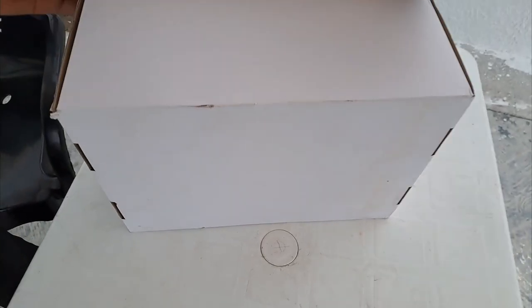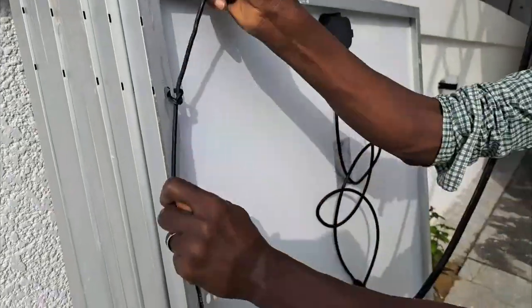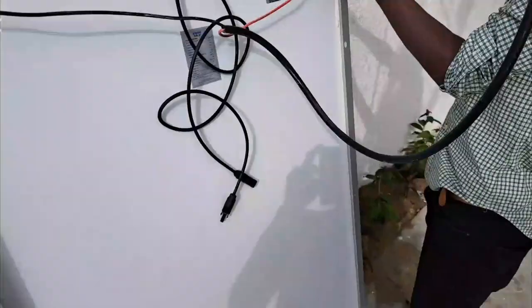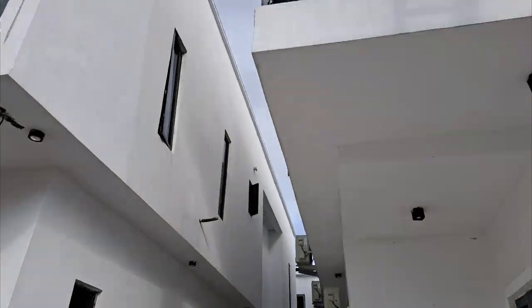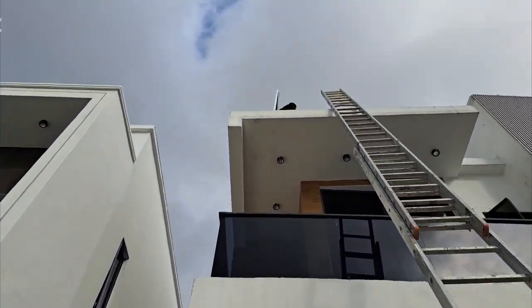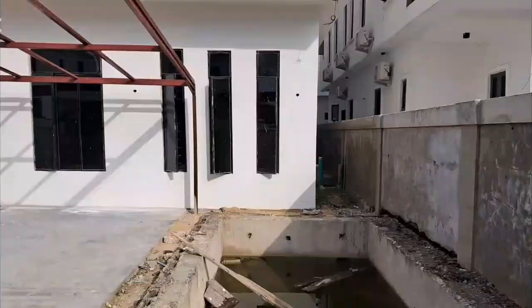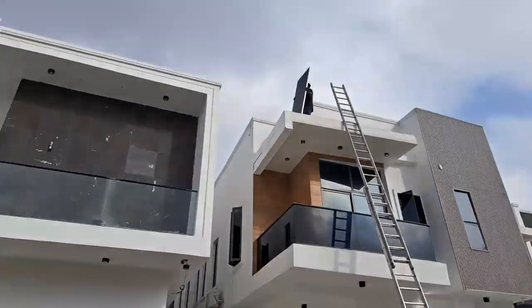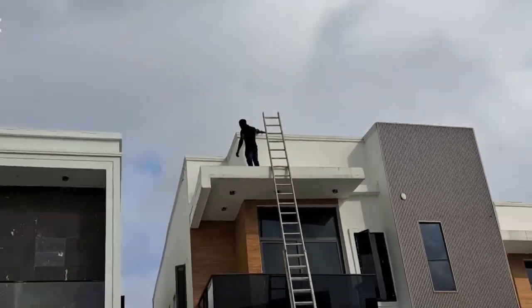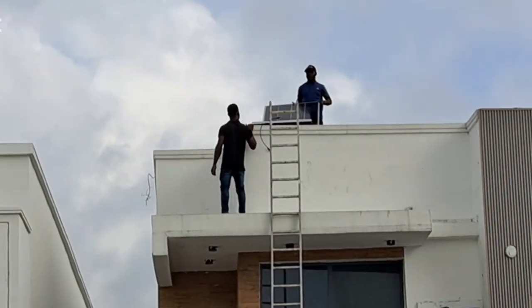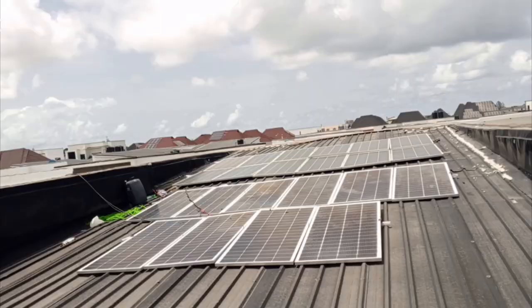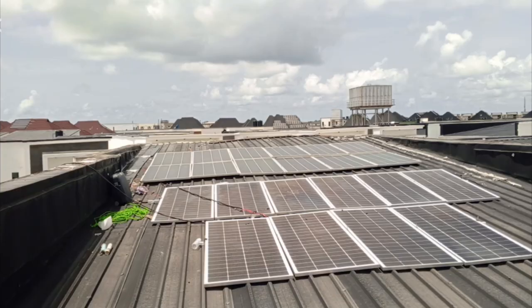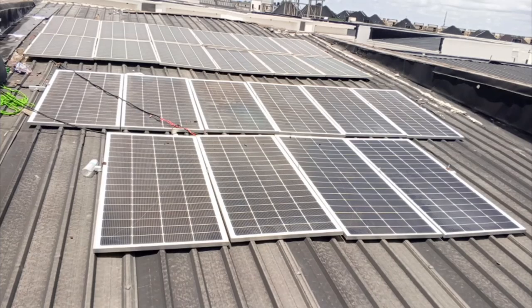On the controller side, it has a capacity to charge with 120 amps. Doing a rough estimation of 50 volts, since battery voltage tends to rise as it charges, 50 volts at 120 amps means we're looking at 6,000 watts entering this battery. At that rate, in 2 hours it will be full. So your solar array can be 6,000 watts.